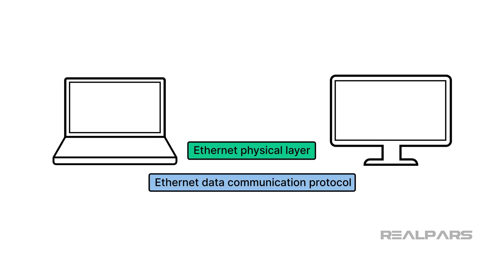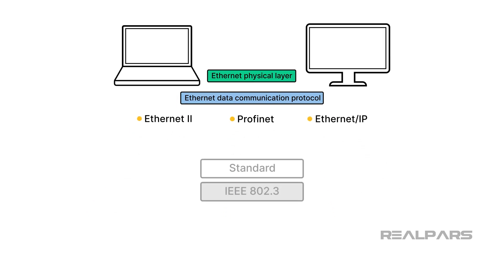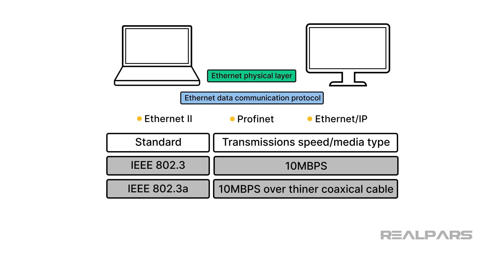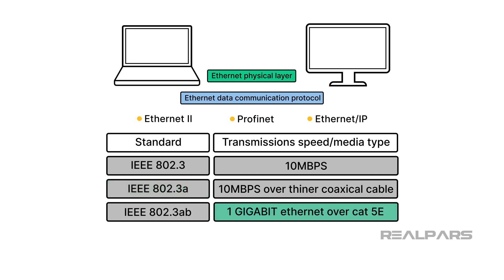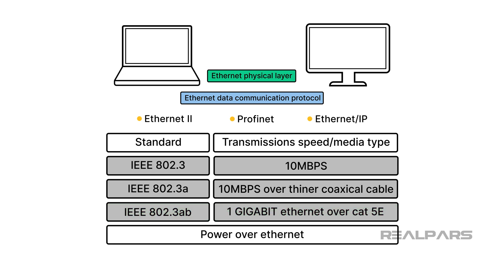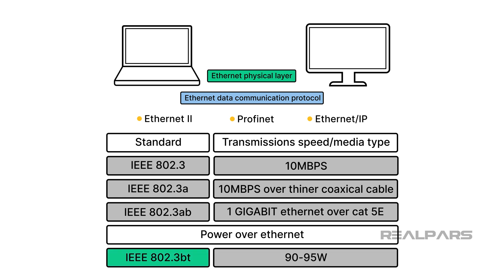An Ethernet physical layer requires an Ethernet data communication protocol. When we refer to Ethernet, it could refer to a number of data communication protocols, including Ethernet 2, PROFINET, EtherNet/IP, and others. All of these protocols fall under the IEEE 802.3 standard. These are distinguished from one another by additional identifiers. For example, Ethernet over coax cabling is identified as IEEE 802.3a. Ethernet over a multi-pair unshielded twisted-pair cable such as CAT5e, operating at 1 gigabit per second, is identified as IEEE 802.3ab. There is also a standard for delivering power over Ethernet, which is IEEE 802.3bt.